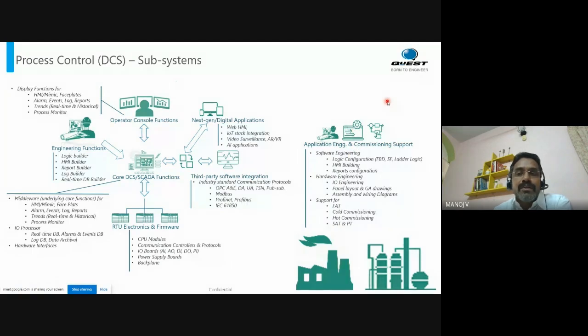It will have an IDE kind of development environment where you have all the functions. Say, for example, square root extraction is a function, PID is another function. You connect one input signal, select and drop the square root extraction function to compensate the flow signal, then take the PID function from the library, put it on your IDE, and connect the output of the square root extraction to the PID. Like that, you keep building.